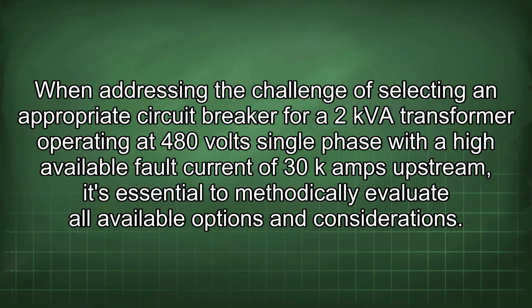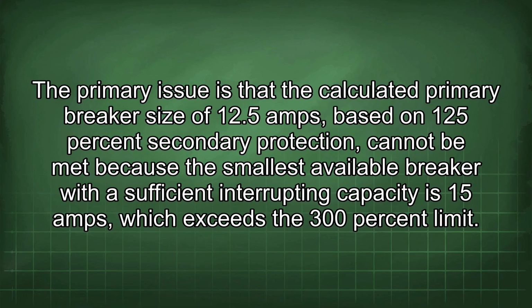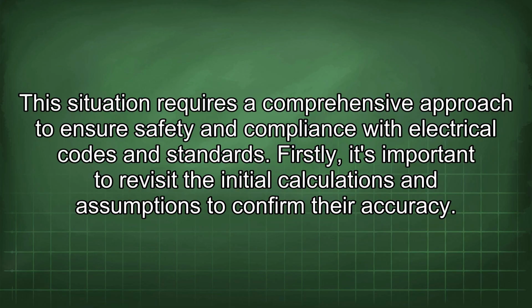When addressing the challenge of selecting an appropriate circuit breaker for a 2 kVA transformer operating at 480 volt single phase with a high available fault current of 30 kA upstream, it's essential to methodically evaluate all available options and considerations. The primary issue is that the calculated primary breaker size of 12.5 amps, based on 125% secondary protection, cannot be met because the smallest available breaker with a sufficient interrupting capacity is 15 amps, which exceeds the 300% limit. This situation requires a comprehensive approach to ensure safety and compliance with electrical codes and standards.